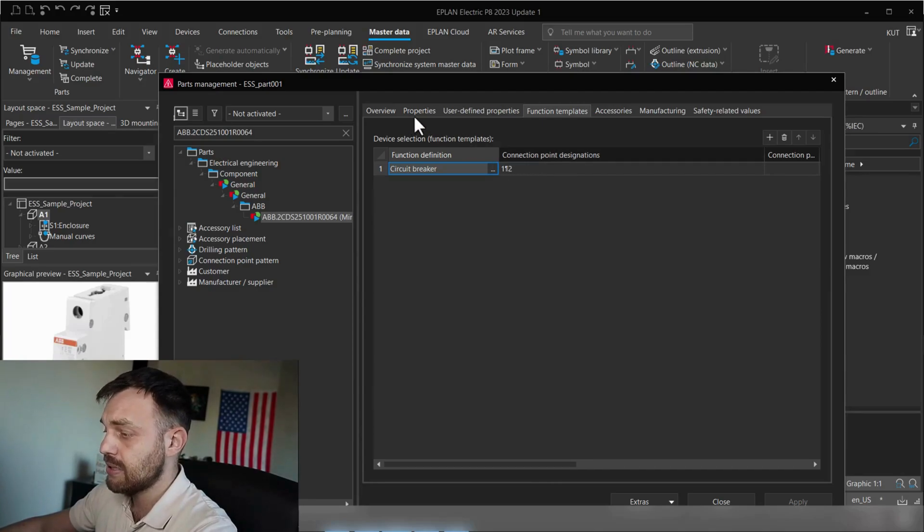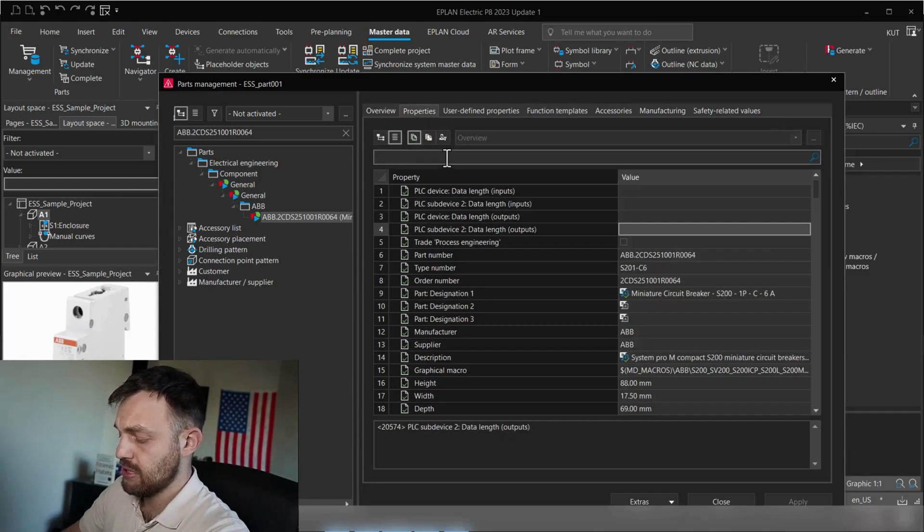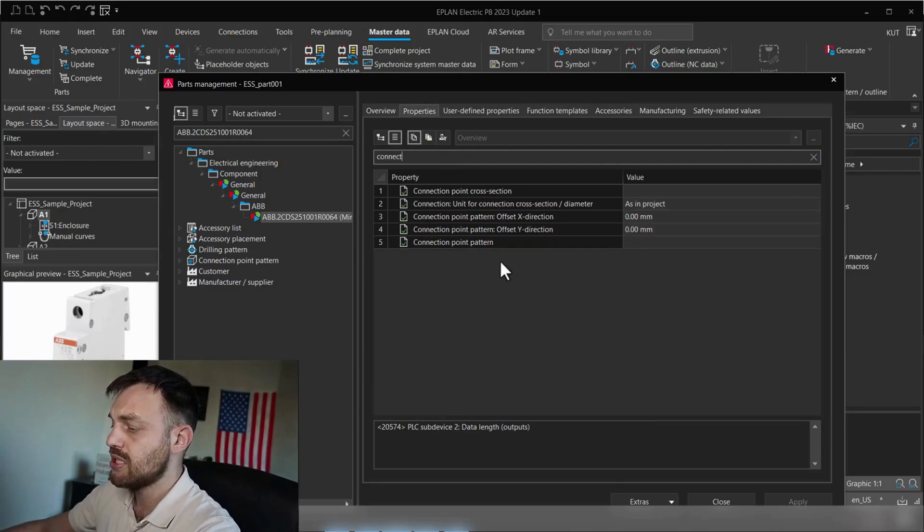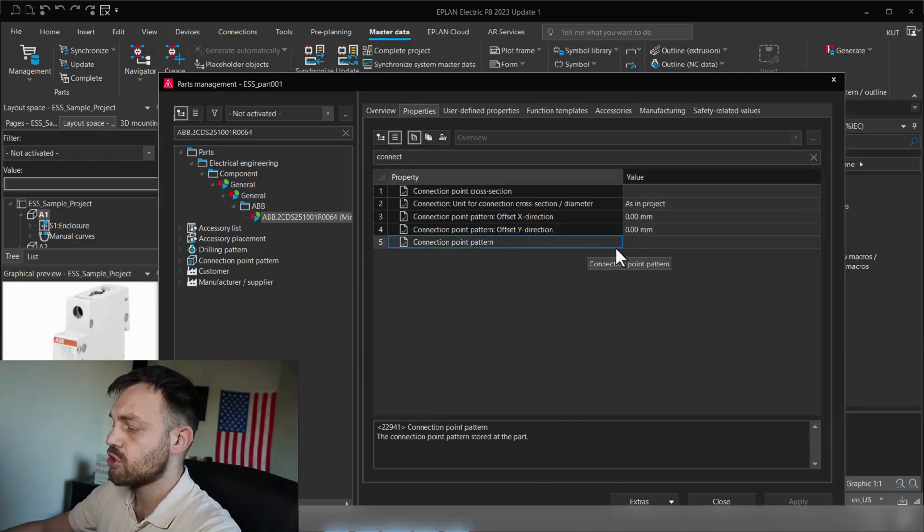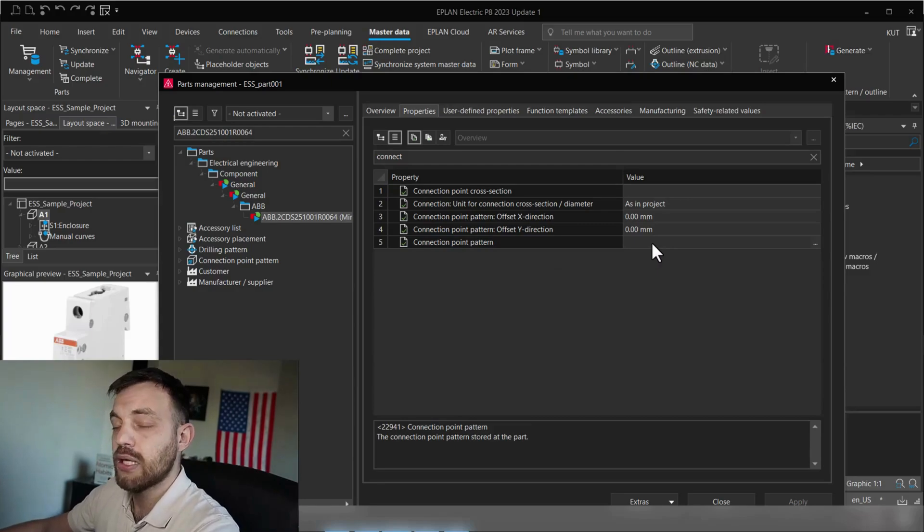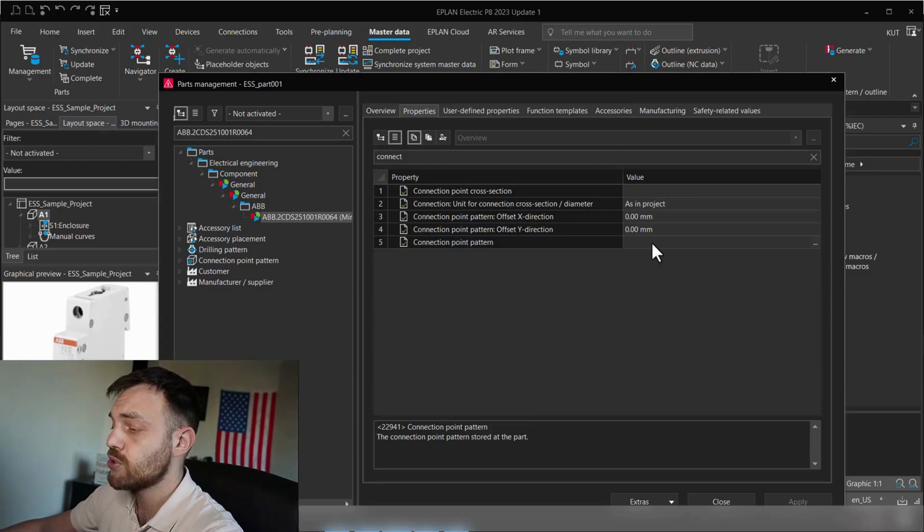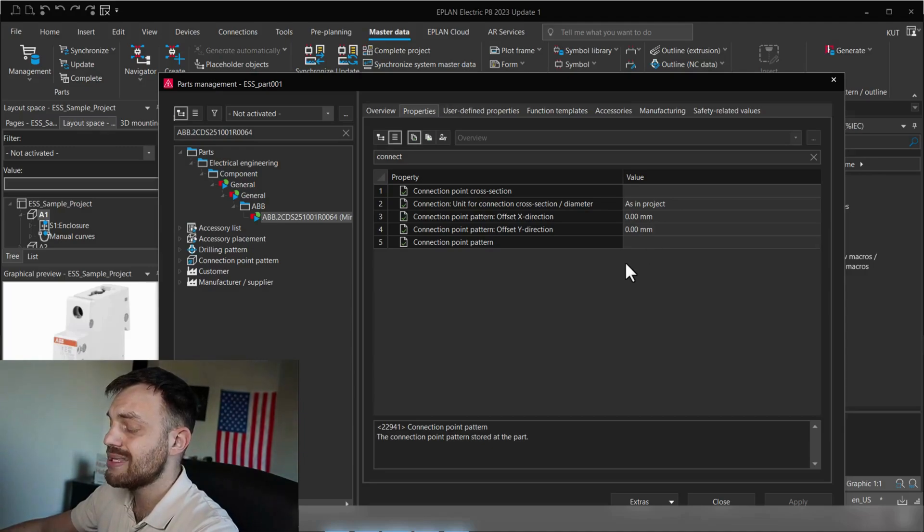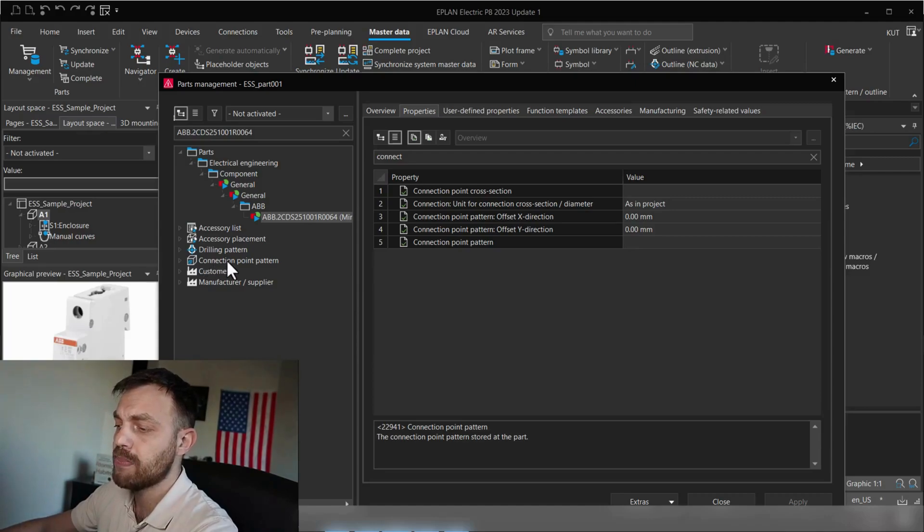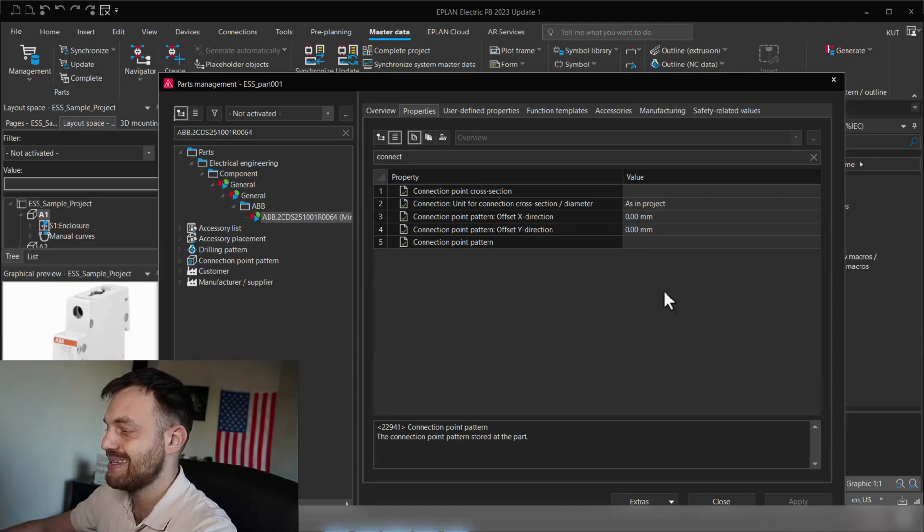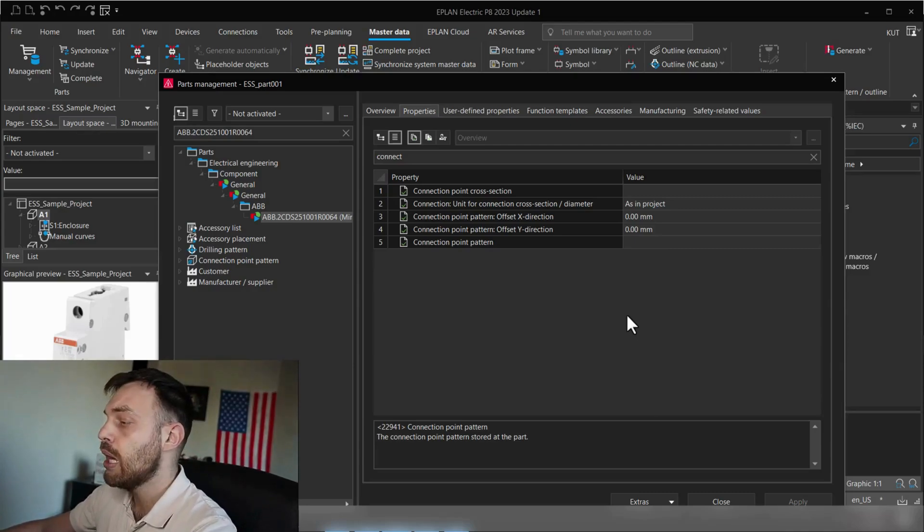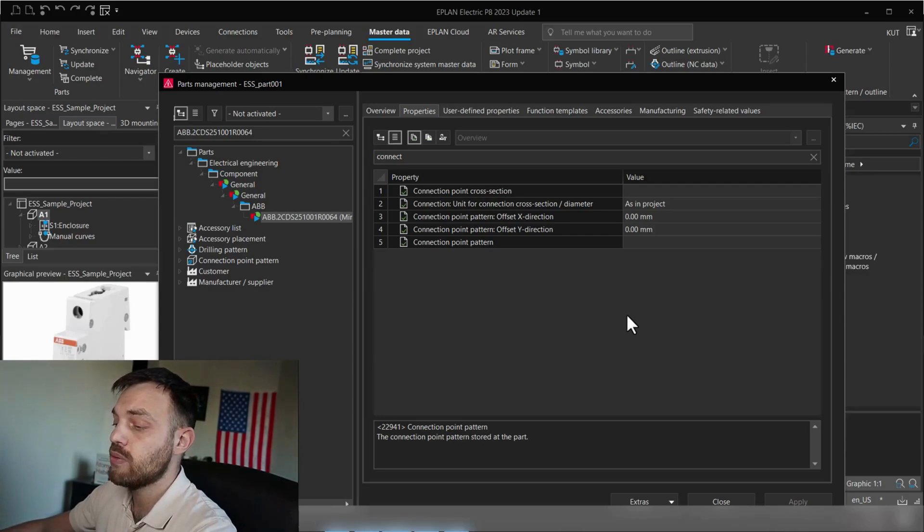Beside that, under properties, you can find, for instance, if you click on the next, you see there is no connection point pattern assigned. There are two types of connection point pattern which you can use in EPLAN. One is a global connection point and one is a local one. A global connection point will be created connection point pattern in the parts management and assigned here. A local connection point pattern will be if you create a connection point pattern in the macro. And this is the exercise which we will do today.